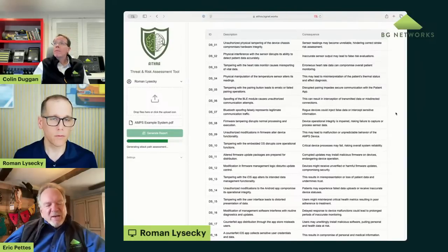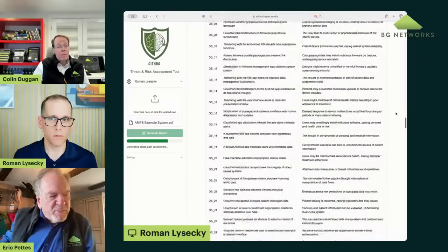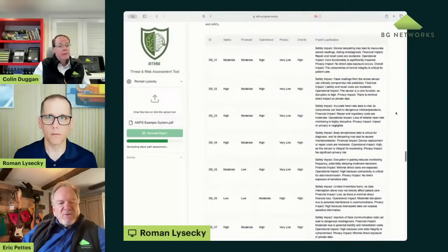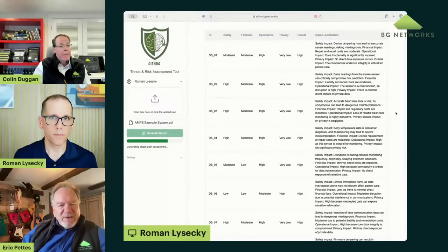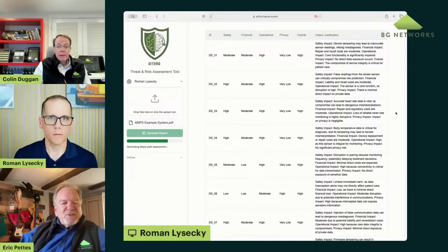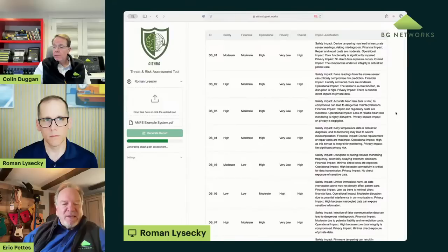Yeah, and when we look at the damage impact from a safety perspective, it is required that you go and grab your hazard analysis or your DFMEA on the safety side, which will exist, because we want to ensure that the threat and risk assessment uses the same language that's used in the hazard analysis. And so the hazard analysis or DFMEA will inform the spreadsheet in terms of language and the extent of the impact. They have to align.